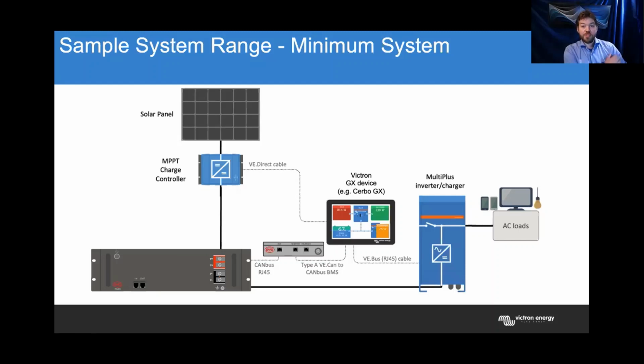I'm sure if you've had experience with lithium batteries before, you'll be aware that it's not just about system voltage anymore. As Harrison mentioned, inside the lithium batteries are a lot of lithium battery cells, and each cell has its own individual voltage, around 3 volts. And each individual cell also needs to be balanced. Now, the BYD system has an automatic system internally for managing and balancing those cells, but if those cells either come out of balance from the factory or they fade out of balance over time, it's very important the rest of the system knows how to manage that situation.